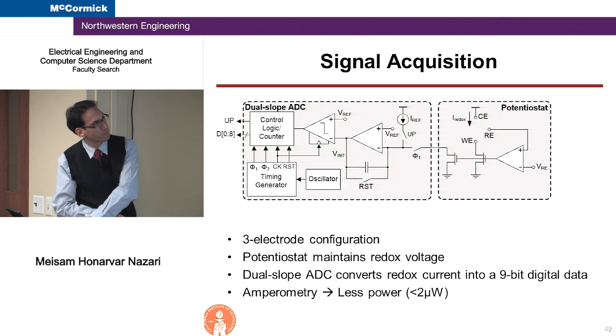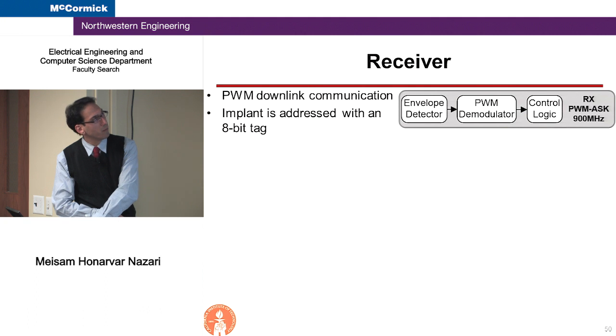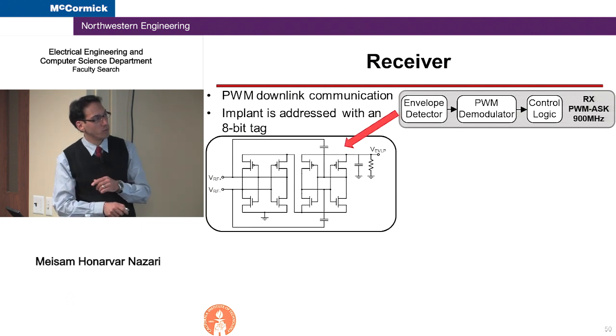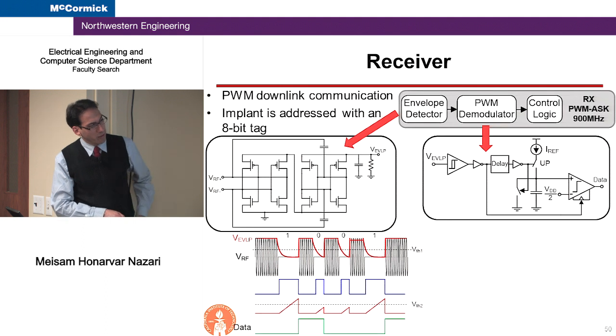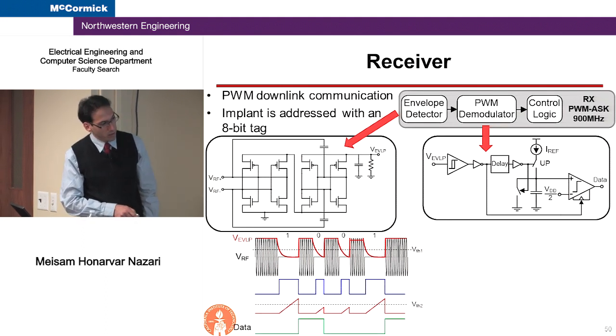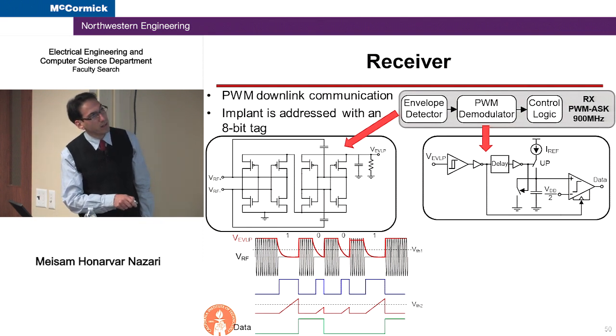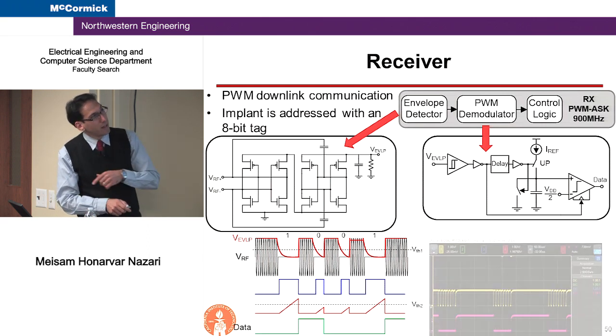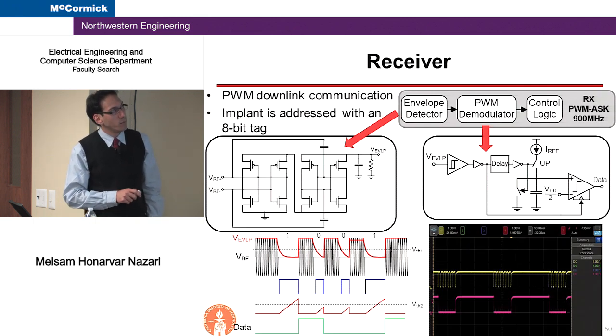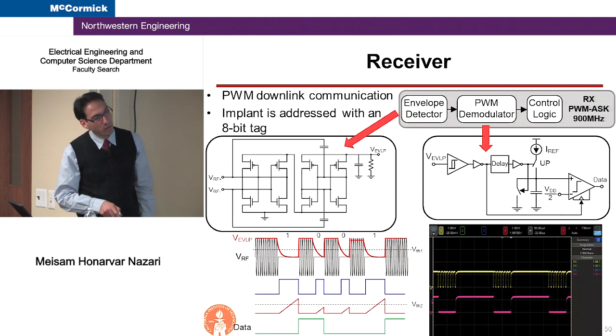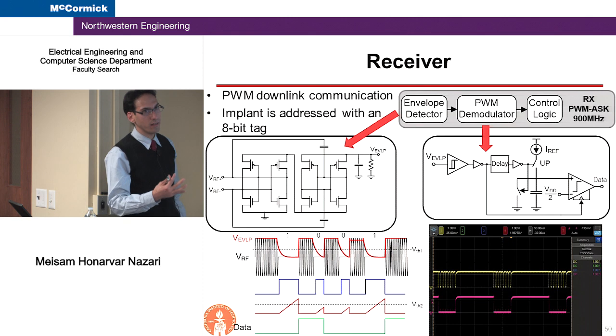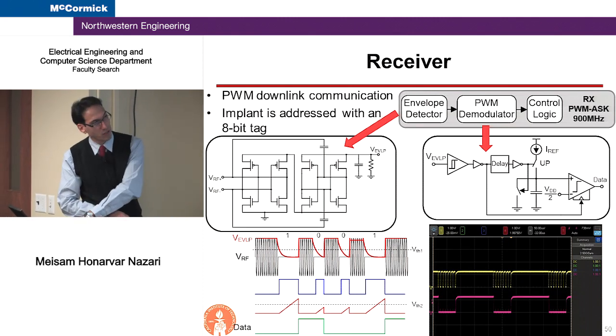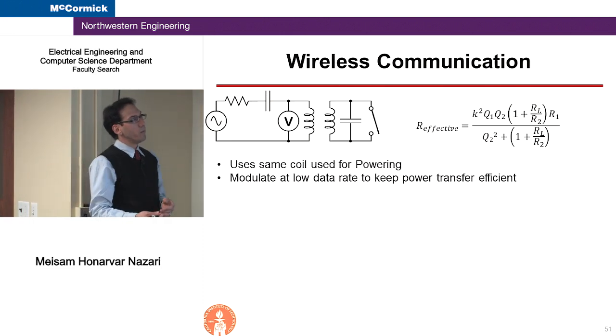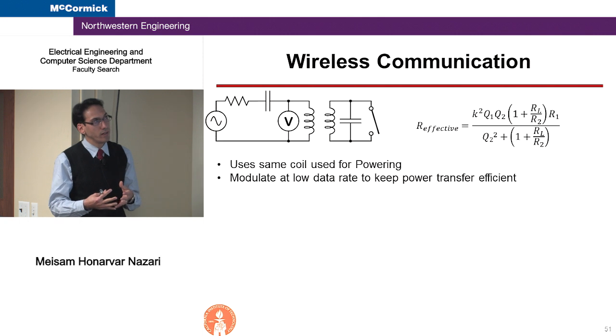They all use amperometry. So on the receiver side, we use pulse width modulation to send data from the outside to the chip. We use a simple envelope detector to do the signal receiving, and then the envelope detector is followed by a pulse width demodulator, and each implant is basically addressed with an 8-bit tag. As soon as the 8-bit tag is received, a trigger signal will be activating the rest of the circuitry in order to make a glucose measurement.